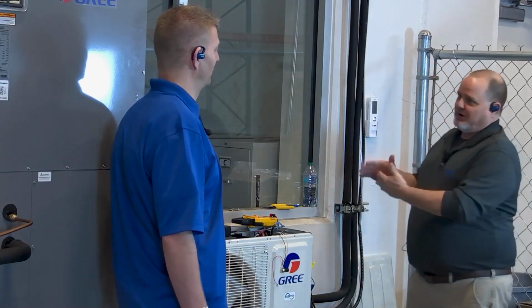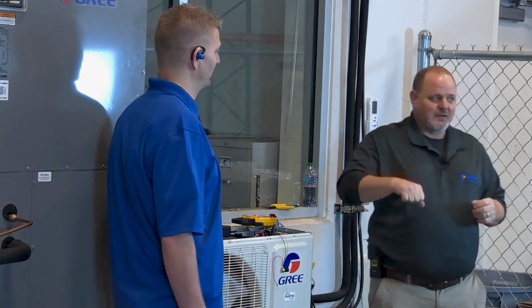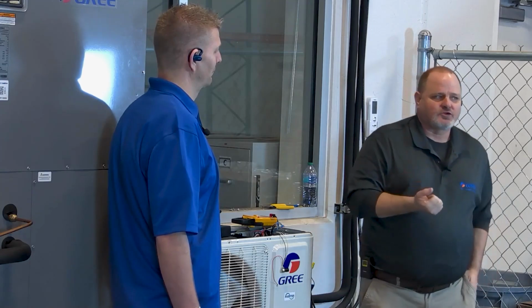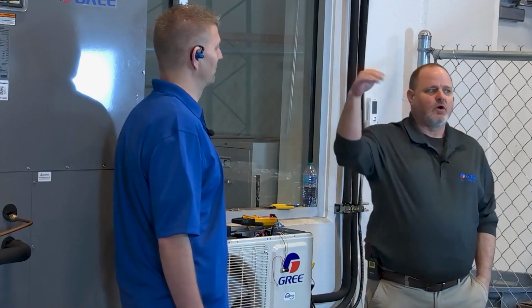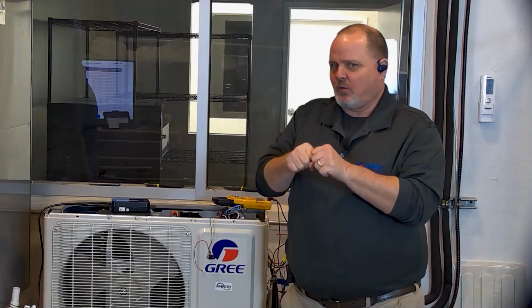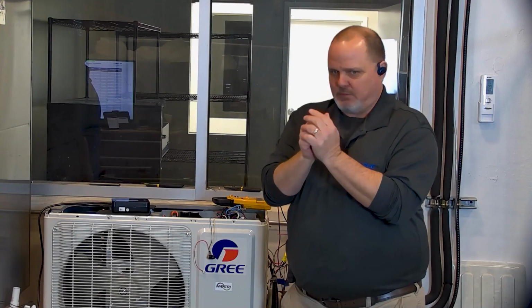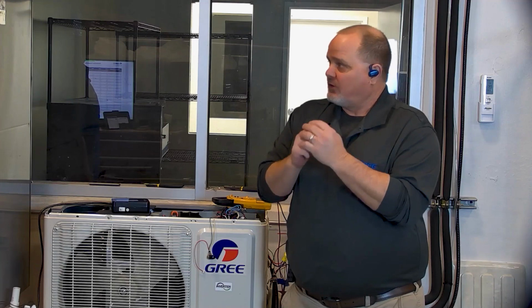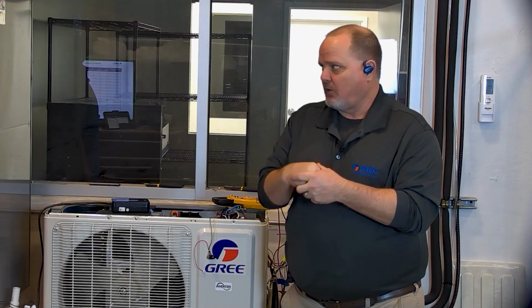Stranded wire is better for that. Same thing with pulling that 14-4 wire. We don't know what kind of bend you're going through and where you're pulling the cable. That 14-4 stranded wire is going to be a lot better for chasing through walls and everything without kinking the wire and causing a voltage bleed between the wires, as you could with solid core. Solid core is going to be a lot worse.